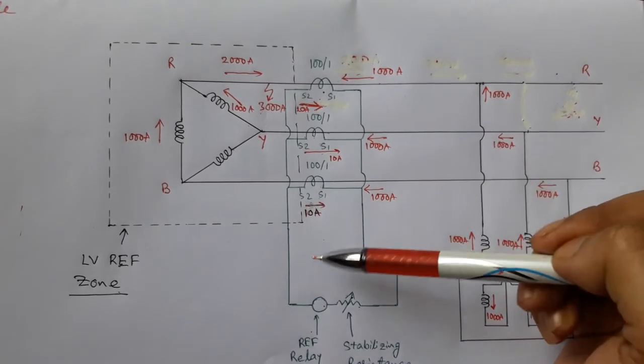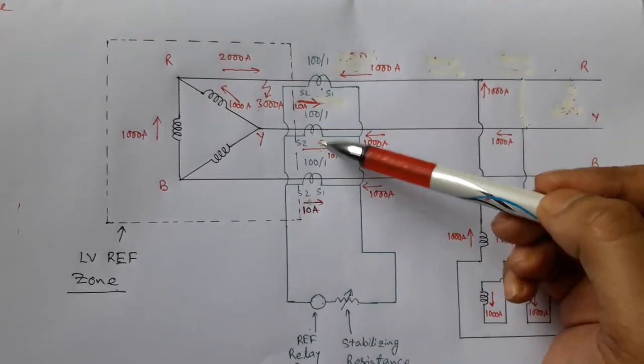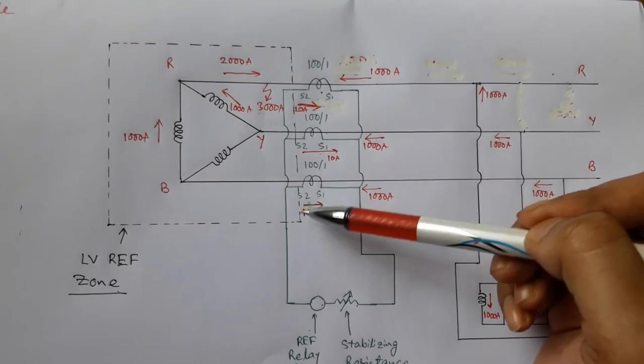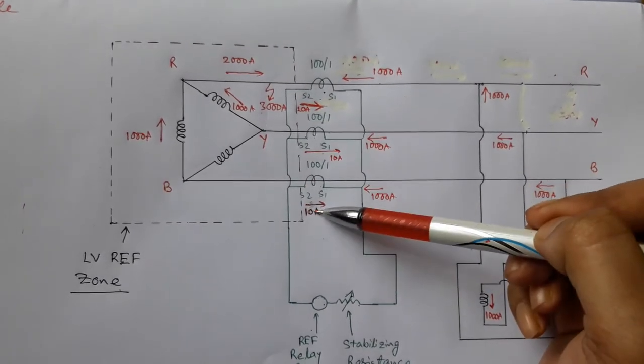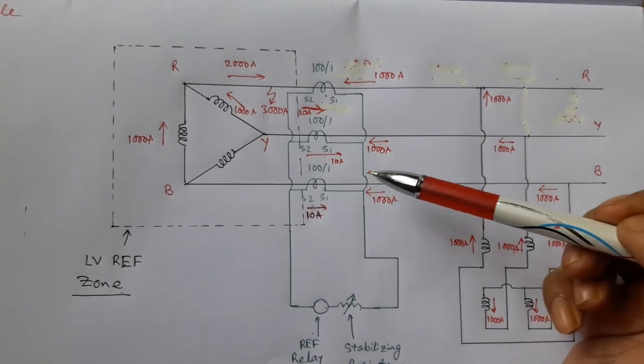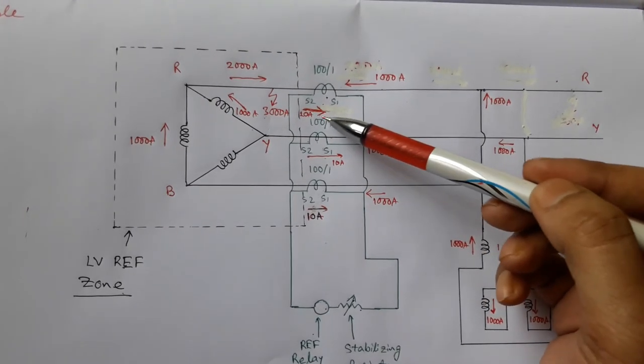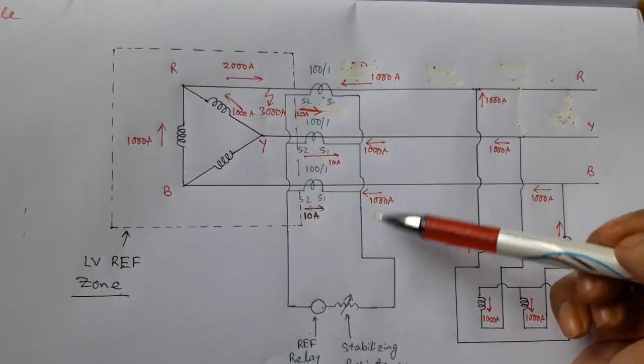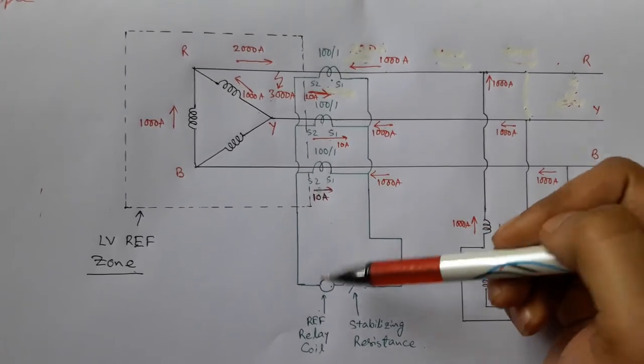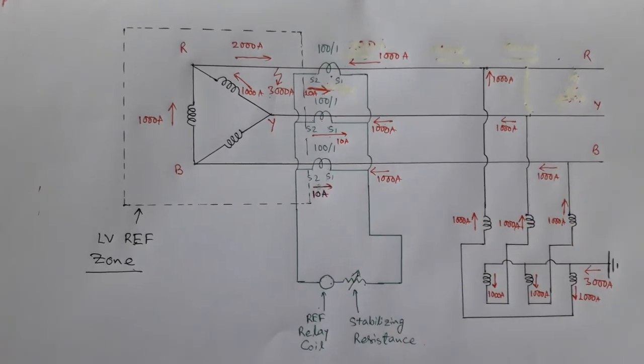So in this case, in the secondary circuit, the current will be like this. And in this case, summation of these three currents is not zero. These three currents will produce a 30 ampere current which will flow in the restricted earth fault relay.